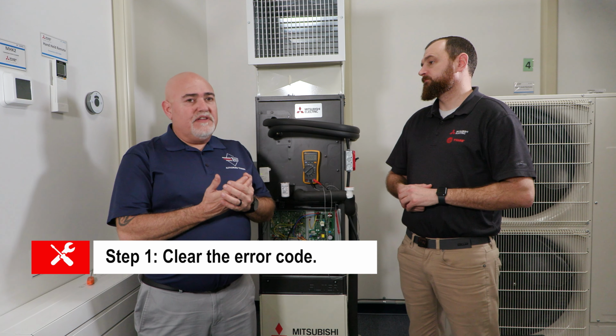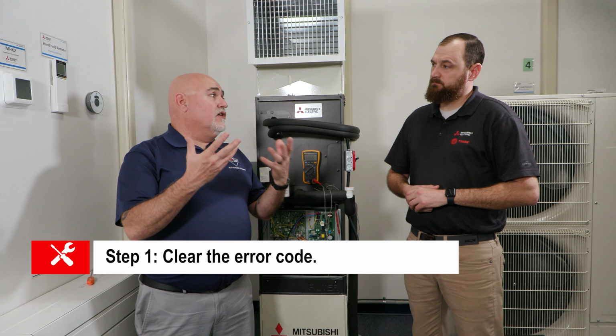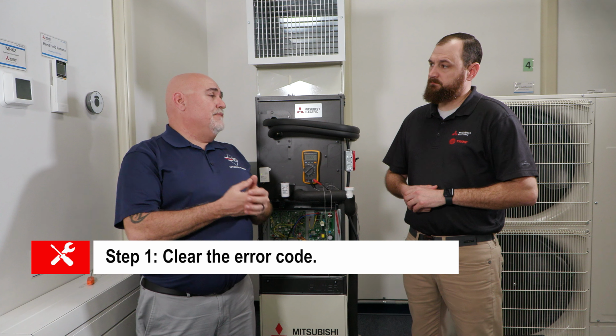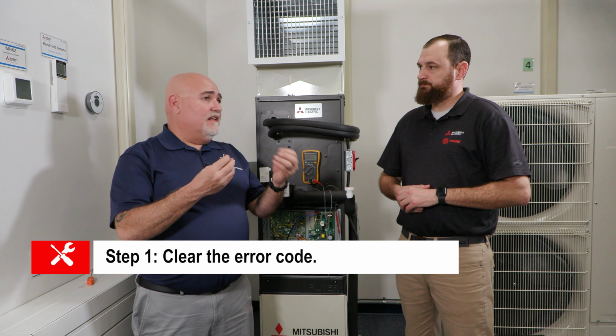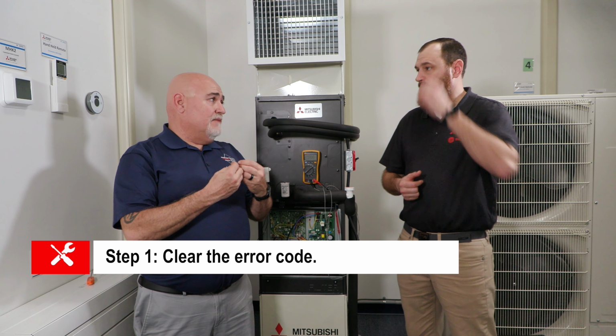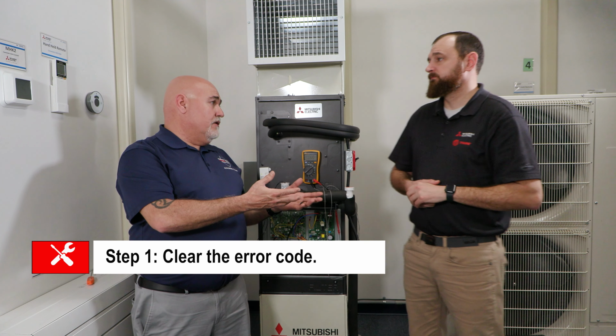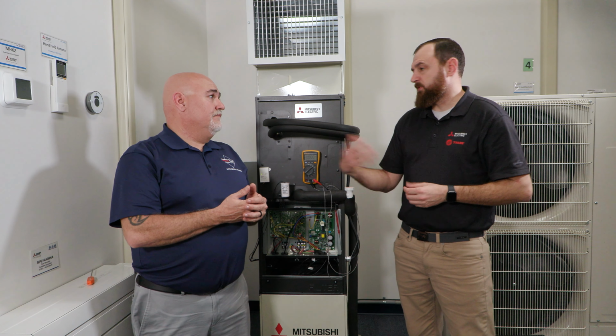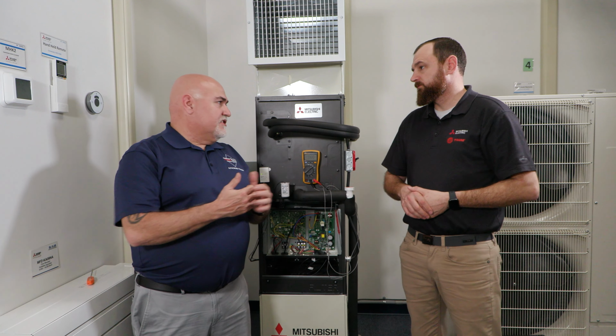And the reason we clear the error code is because the error code can actually cause voltage readings to be bogus. What I mean by that is some of the voltages that you're going to be reading could be skewed by that error code. And so what would be the best practice to clear an error code? Reset the disconnect, okay. Right?